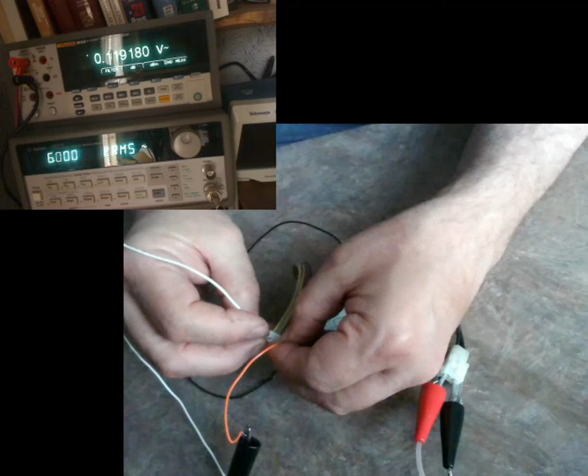Alright, and I'm just going to go across. Here is the one winding, right? It was supposed to be 165 millivolts, and it's 172. If I go across the entire winding, it's twice that. So this transformer definitely is working at this lower voltage.